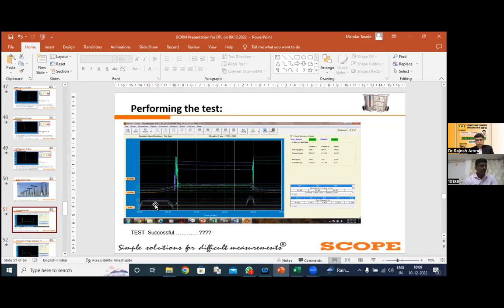Because whenever we are performing the coil current operation on the CB, this is the combined test actually. Whenever we are performing the coil current test on the CB, we are getting the maximum coil current. We have the station DC available with us. So at that time, with the help of Ohm's law, that is R is equal to V by I, we can calculate the resistance value of the coil, which is actually specified by the manufacturer, whether we are getting the coil current value within the limit or not.